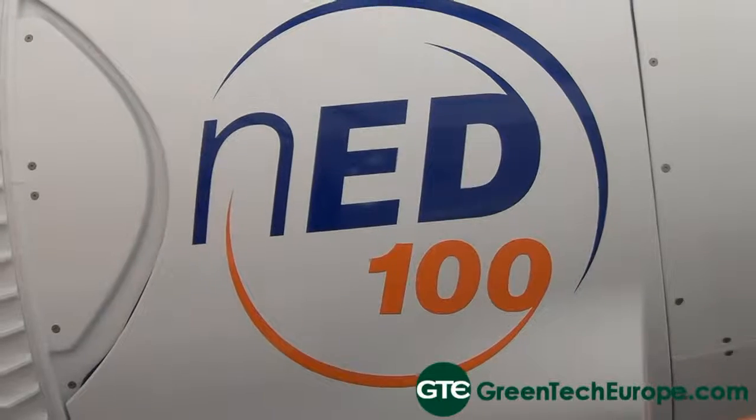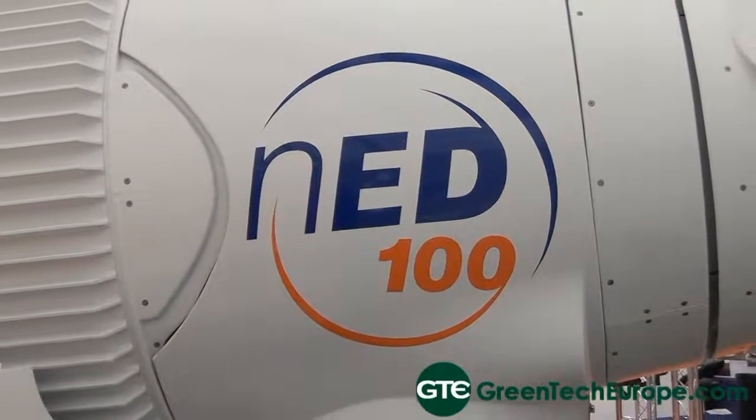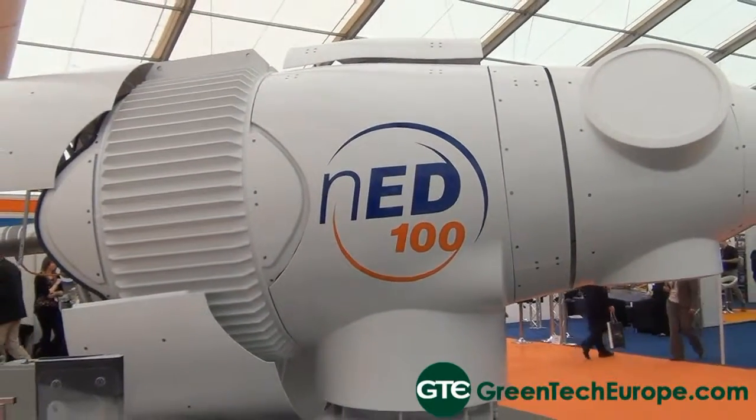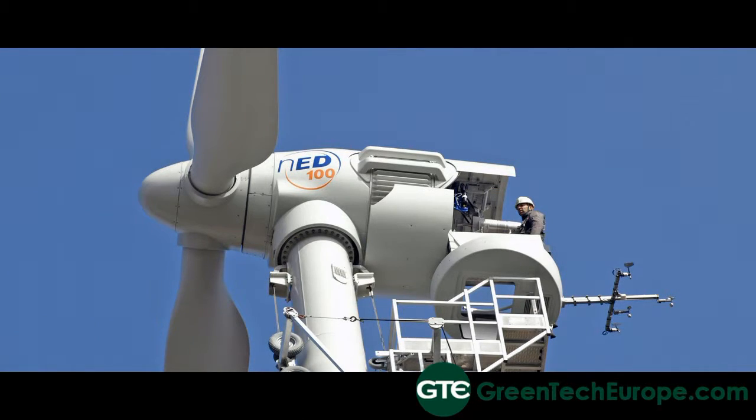Can you give us a bit more information about your nED 100 and what other technology you've developed? The nED 100 is a 100 kilowatt wind turbine. It's classified as a medium wind turbine. It is a direct drive pitch control machine. It has a permanent magnet generator and it's a fully electrical machine with no hydraulic system inside. Basically, the nED 100 brings all the technological advances made in recent years in the big wind industry and packages it into a medium wind machine.